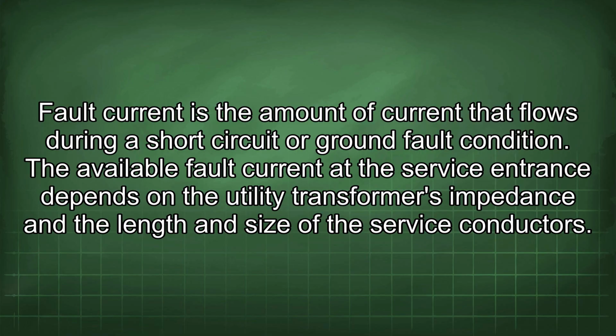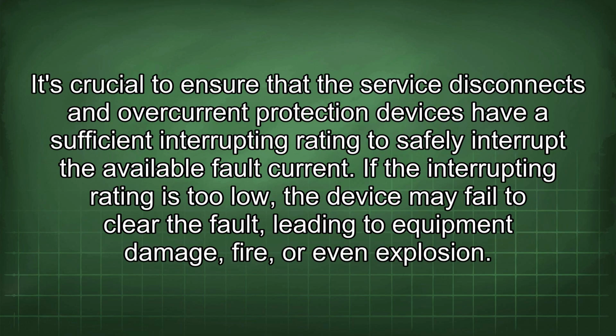The available fault current at the service entrance depends on the utility transformer's impedance and the length and size of the service conductors. It's crucial to ensure that the service disconnects and overcurrent protection devices have a sufficient interrupting rating to safely interrupt the available fault current.